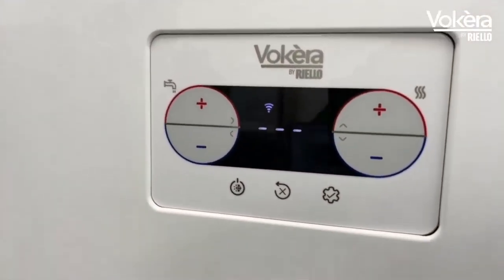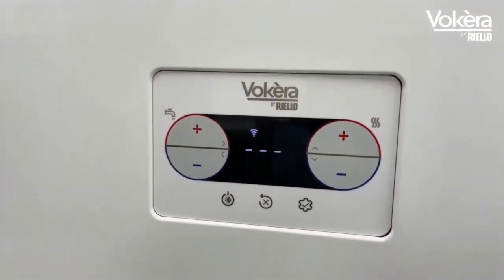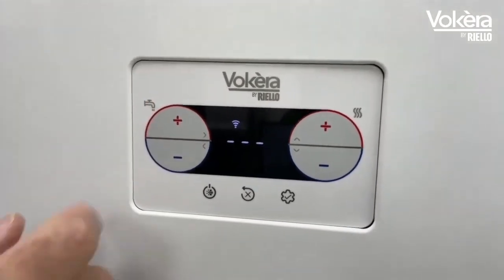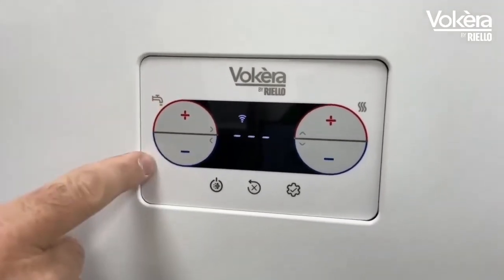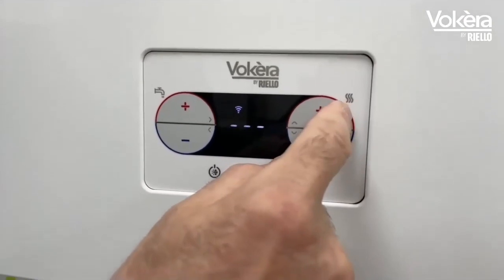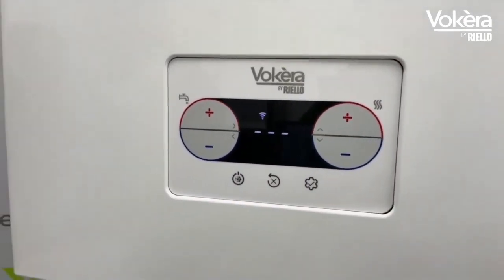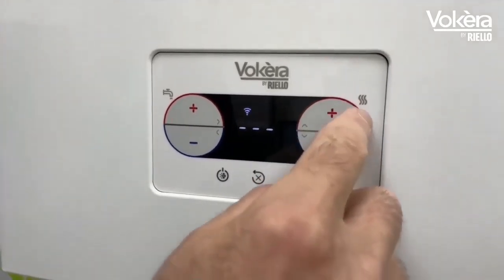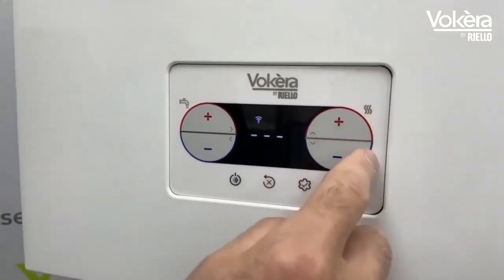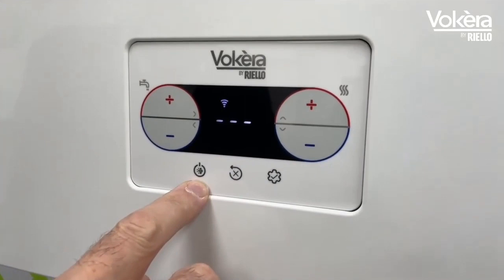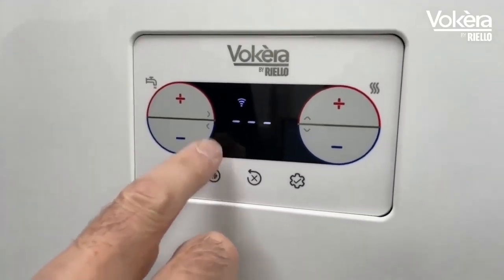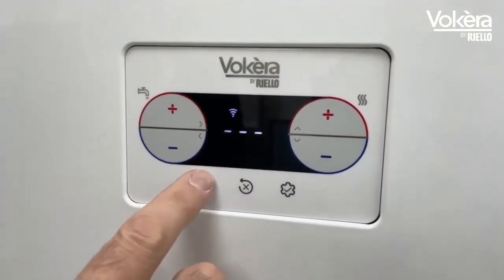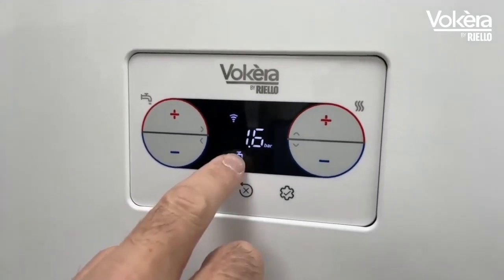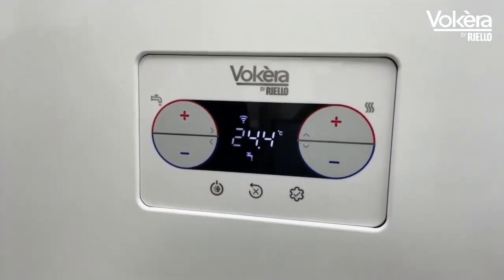If the Wi-Fi is connected, obviously you'll see this. Hot water temperature here under normal conditions, heating temperature adjustment here, or if you're using dual weather compensation, that would be your internal nominal temperature adjustment. Mode, so at the one, this is standby. One press brings you on to domestic hot water. Second press brings you hot water and heat.